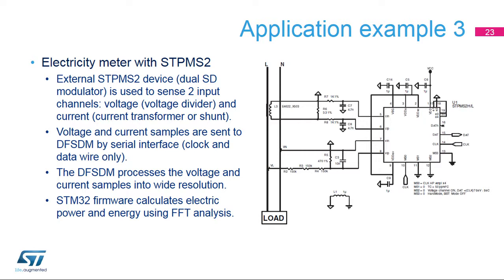The clock is provided by the DF-SDM and can run up to 4 MHz. The DF-SDM then processes the voltage and current channel 1-bit data streams into output data with higher resolution and slower data rate. Finally, the firmware uses FFT analysis to calculate the electric power and energy from the current and voltage samples.